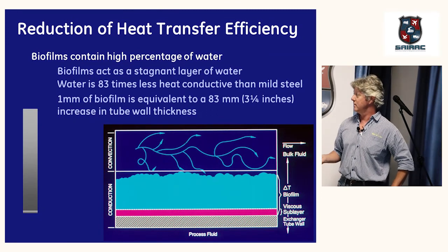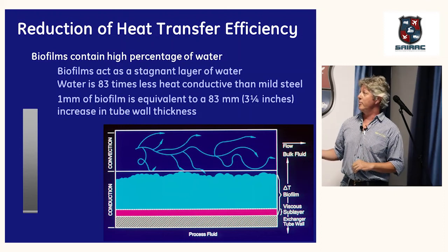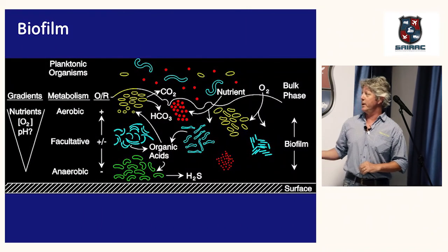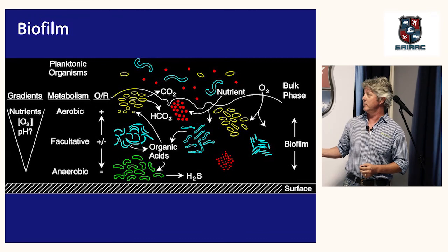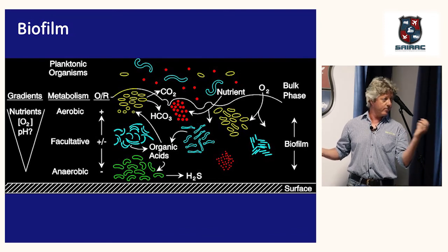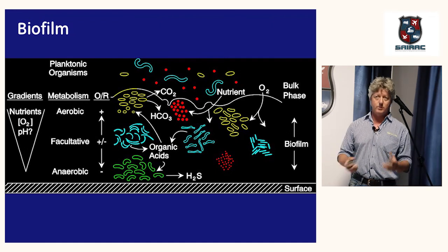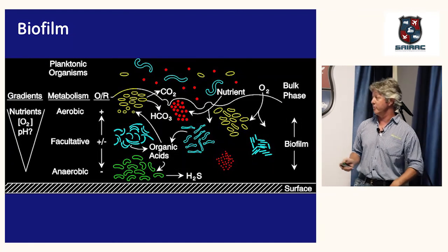What is the red layer? The red layer is where the bacteria adhere to the system. Okay. Many times the top layer of the biofilm could be dead bacteria. Okay. But it's still stuck to the sublayer, which is connected directly to your metal system. So if there is a biocide in your system, it'll kill it off, but it won't always slough the bacteria off your system. For that, you're going to need something else. So you could end up with a dead layer there, which has got a lot of water entrapped in it, and which inhibits transfer of heat.